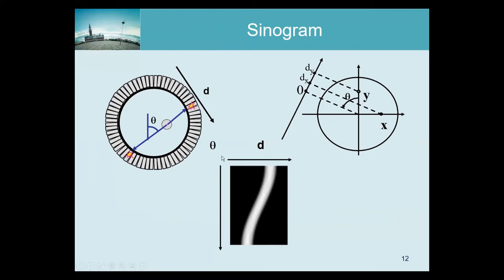And so in this case these data are organized as projections over 180 degrees, which is also what you would always have in PET. A gamma camera can rotate further and acquire also projections at the other side of the patient, and they will be different because the effect of attenuation in both directions is different. In SPECT, therefore, it's meaningful to acquire over 360 degrees, so then you will have a sinogram that starts here, goes all the way up, and then all the way back. So you will see a full period of that sine, and the first half will look a bit different from the second half because of attenuation.